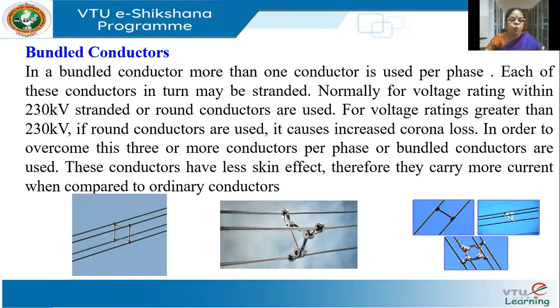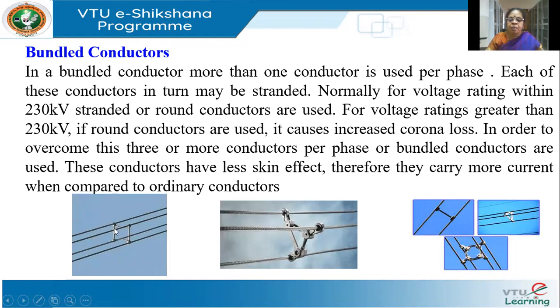In bundled conductors you may have two, three, four, or six conductors per phase arranged like a hexagon. Between the lines at suitable distances you will have spacers to prevent conductors from swinging and hitting each other. All conductors in the bundle carry current of the same phase. Bundled conductors have less reactance due to more GMD — geometric mean distance — which will reduce the voltage drop in the line, improving the voltage profile.